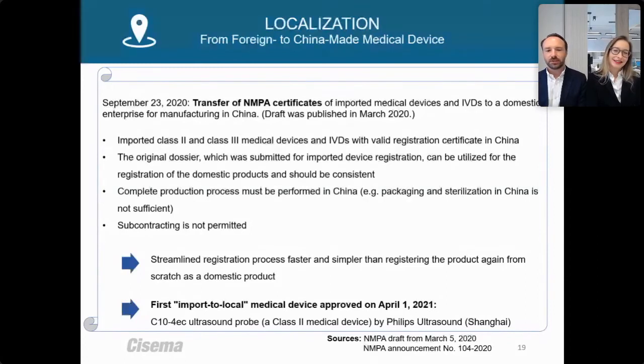And the main raw materials and production processes shouldn't change, and the quality management system must be consistent with the previous one. NMPA focuses on the consistency and traceability of the quality management system, the QMS. Successfully registered foreign-owned enterprises must indicate the registration number of the imported device from the original registration in the new registration certificate. The manufacturing in China should include the complete production process from the start phase to the end phase of the product. This means that not only performing packaging and sterilization will be sufficient, so the manufacturer should be able to control the product quality throughout the defined main producing process. Products should be produced by foreign invested enterprises established in China by the registrant, whilst on-site production is possible through subsidiaries and joint ventures, but subcontracting is not permitted for the scope of transferring the manufacturing from overseas to China.